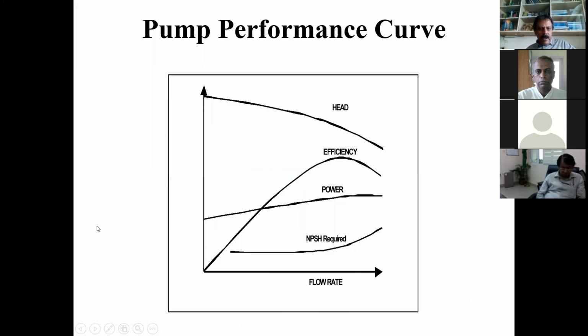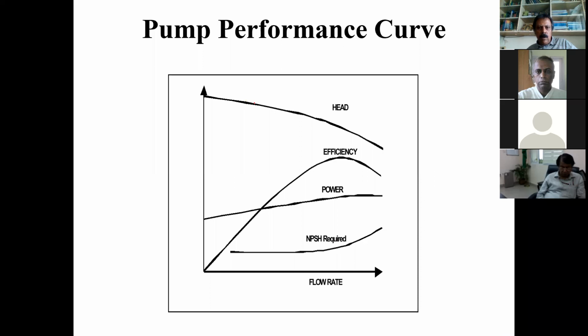Now, if you look at the characteristic curves, this is very important as far as evaluation of pumps is concerned. You will find that in many cases in the industries, these curves are originally supplied along with the pumps, but they go missing quite often. So you don't get to see these curves in the industry. When you go to the industry, the pump is there, but these pump characteristic curves are not there. So it's very important to keep a set of these pump curves as given by the manufacturer. The first thing is to demand these curves from the manufacturer when you buy a pump. The second thing is to store them safely so that they can be made useful for later analysis.